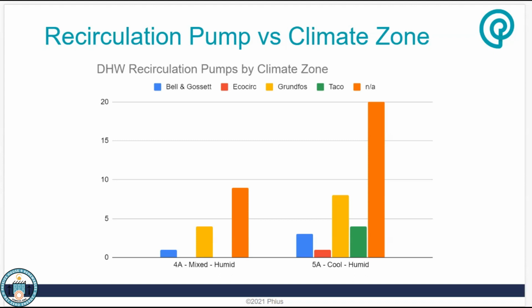And then the last one is NA, because there's a big chunk of projects we see that don't even require this on-demand recirc because they've got a compact design. They're going to meet that WaterSense test without the recirculation. It's basically having better location of your domestic hot water tank or system in comparison to where the fixtures are. Typically as a rule of thumb, if your fixture is more than 50 feet away with a half-inch pipe, you're probably going to need a recirc line because it's going to take too long to get hot water out of that tap.